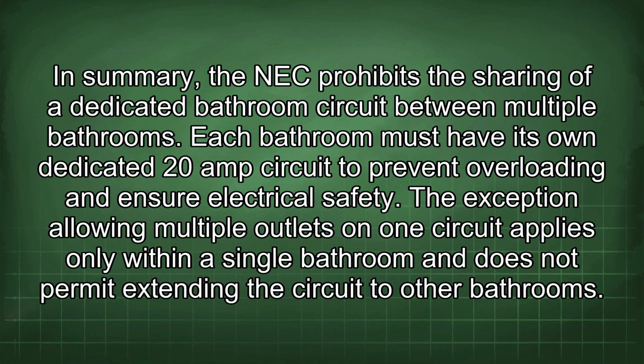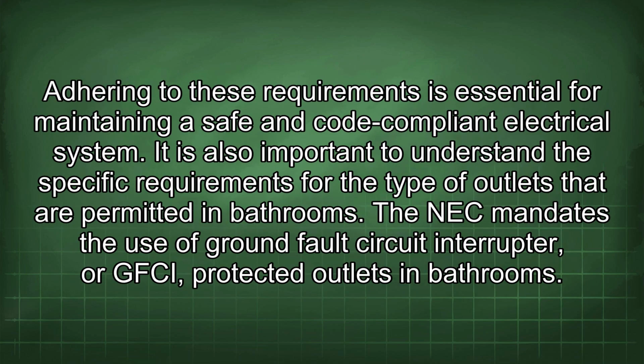In summary, the NEC prohibits the sharing of a dedicated bathroom circuit between multiple bathrooms. Each bathroom must have its own dedicated 20-amp circuit to prevent overloading and ensure electrical safety. The exception allowing multiple outlets on one circuit applies only within a single bathroom and does not permit extending the circuit to other bathrooms. Adhering to these requirements is essential for maintaining a safe and code-compliant electrical system.